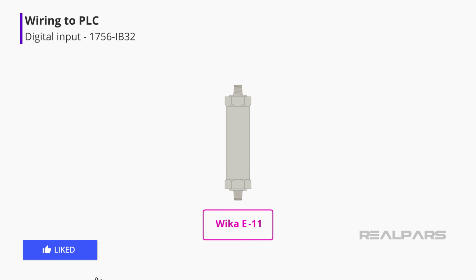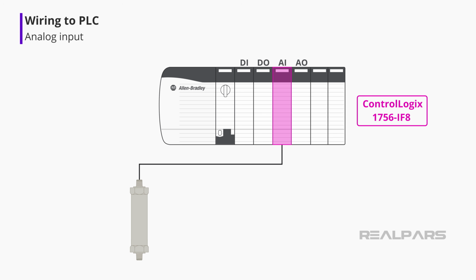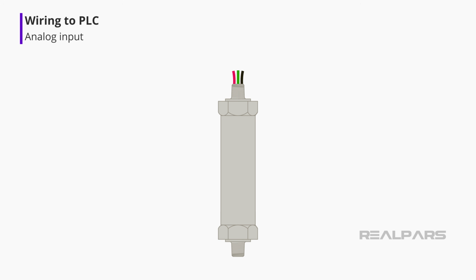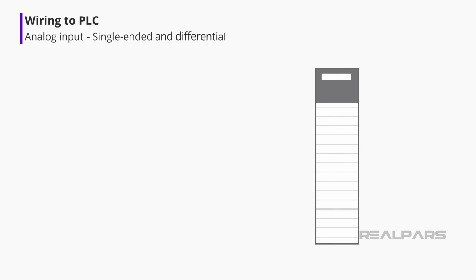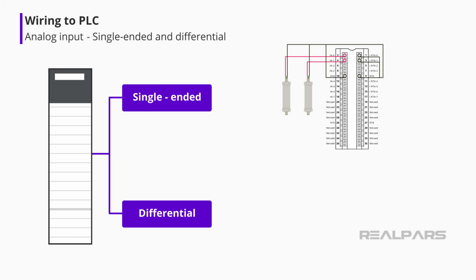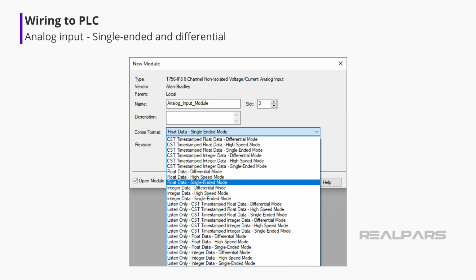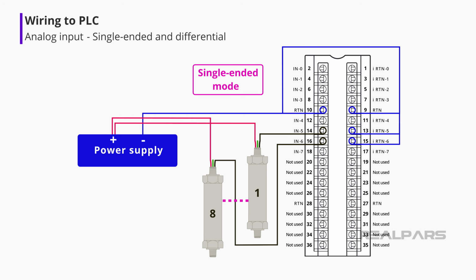Okay, let's move on to wiring pressure transmitters to a PLC analog input module. We'll look at wiring a two-wire Wika E-11 pressure transmitter to a ControlLogix 1756-IF8 analog input module. On the transmitter, the red lead is current in, and the black lead is current out. The analog module can be wired in two possible modes, single-ended or differential. The selection is important as it determines how the module is physically wired. Our module is configured for single-ended mode. In single-ended mode, we can connect 8 two-wire transmitters sharing one power supply. Each transmitter connection is referred to as a channel.